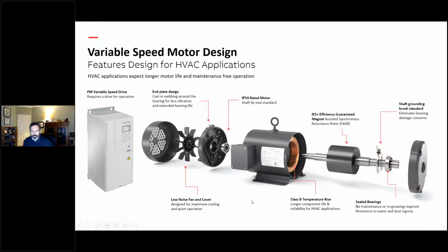So, fundamentally, that's how this technology gets you to a higher efficiency level. There are other design features in this type of motor construction that a standard induction NEMA motor doesn't allow you. Based on HVAC applications, they expect longer motor life and maintenance-free operation. So you design the motor, in addition to being high efficiency with the rotor design, so that you don't have unexpected downtime or maintenance issues. Also in HVAC systems, noise is an issue. So, from a design standpoint, you want a low noise fan and cover, and a smaller fan size on it.